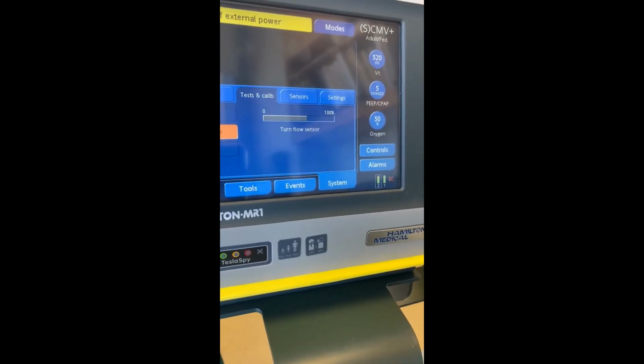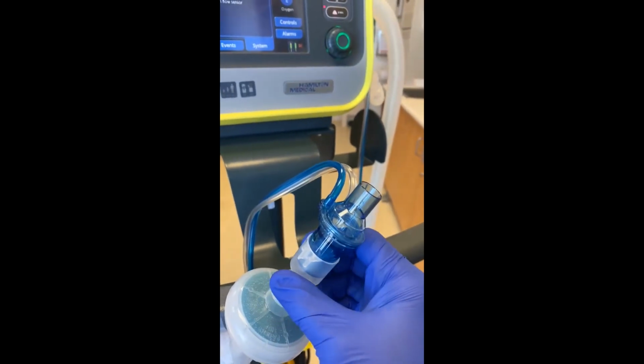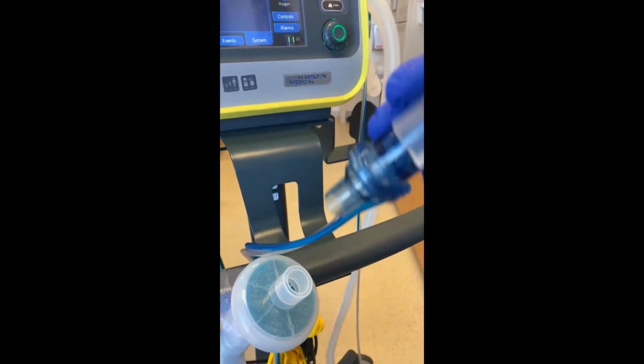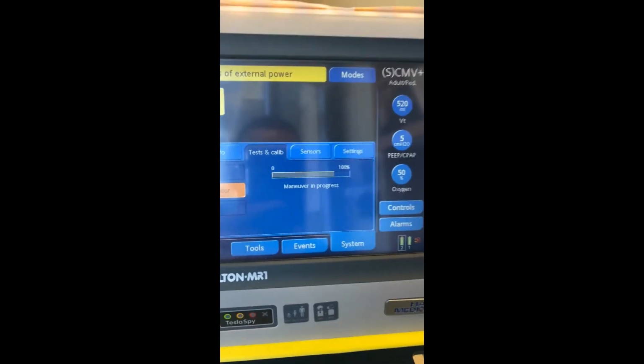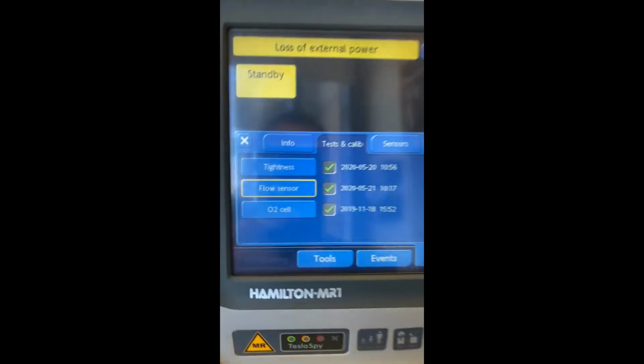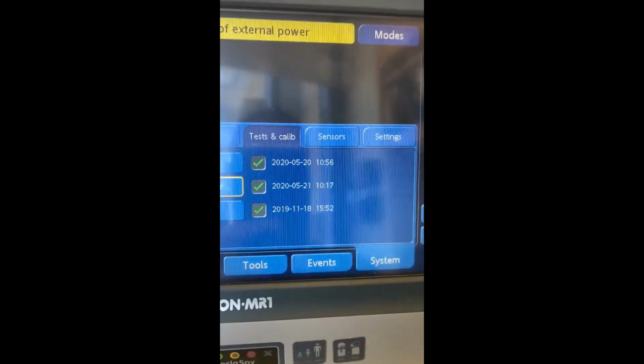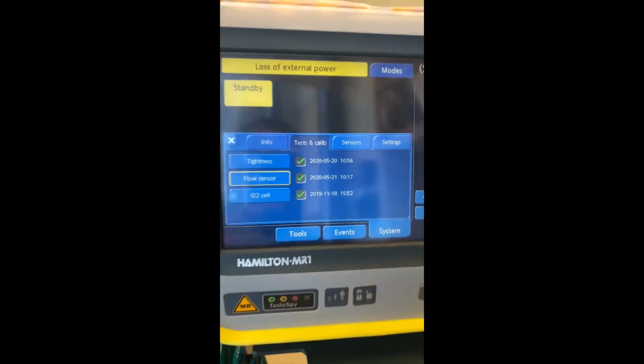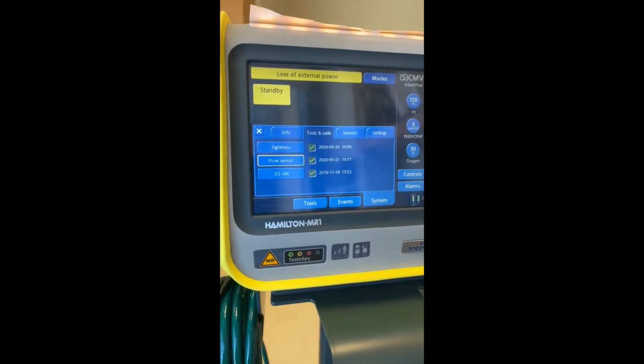So now it says to turn flow sensor, so we're actually going to flip it back over again. So I'll take it out and flip it. So now that it's flipped, you're just gonna wait for the bar to get all the way to 100%. And then it's gonna show you that the flow sensor passed.